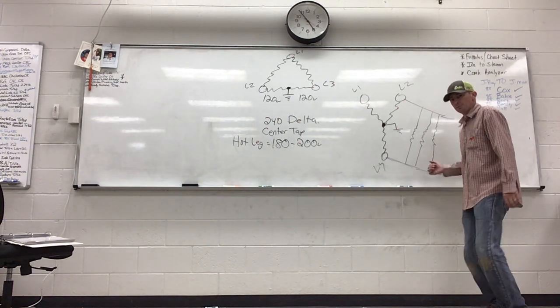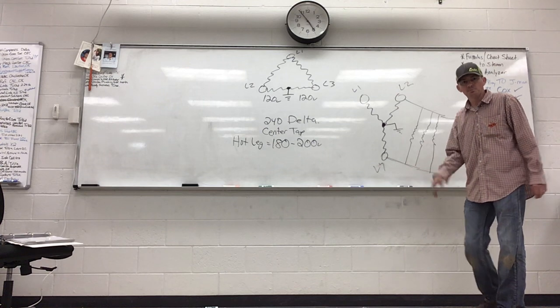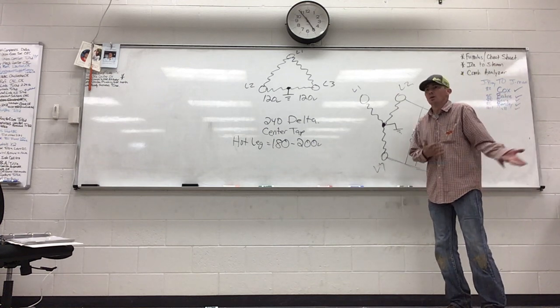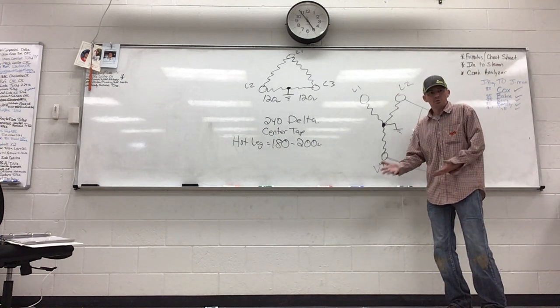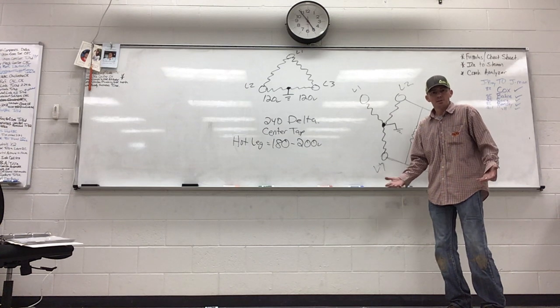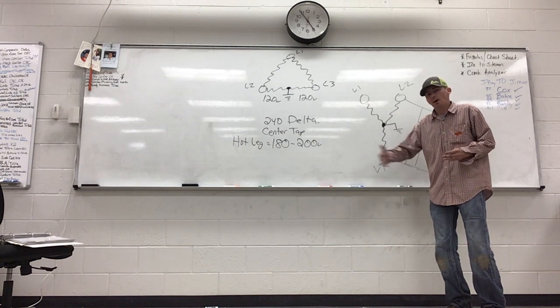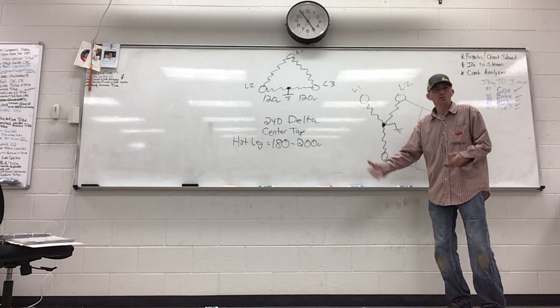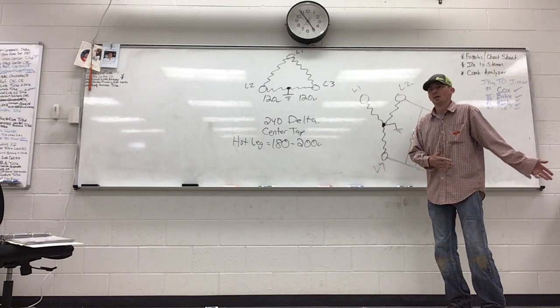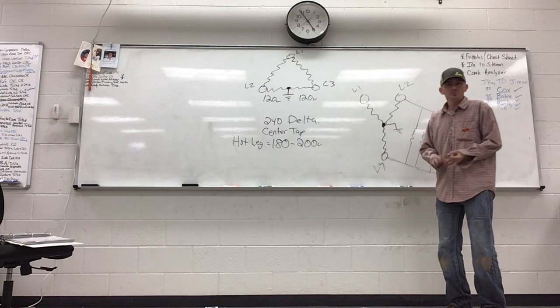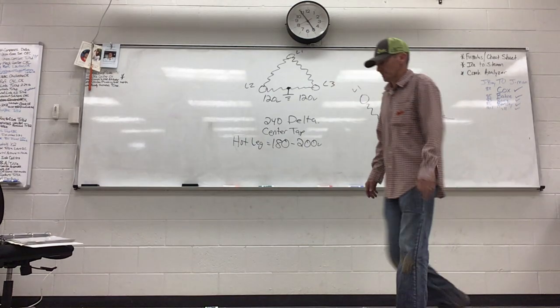And just wire it up and flip the power, slap it on the butt, and wish it the best of luck. We're not going to do that. We're going to crawl this thing and make sure there wasn't something prior going on that caused this motor to fail, right? It could be a dirty power issue, it could be a phase imbalance issue, and all this other good stuff.